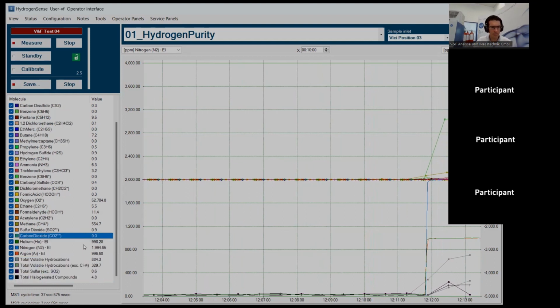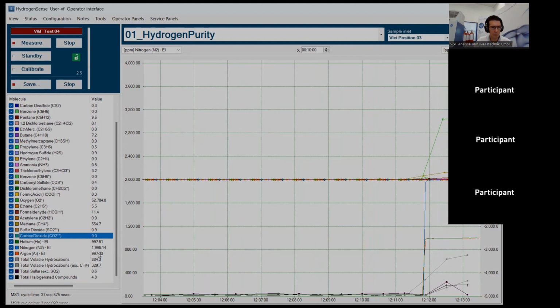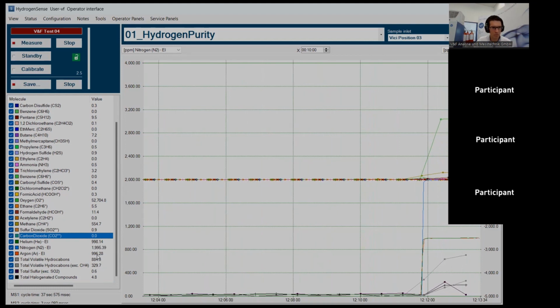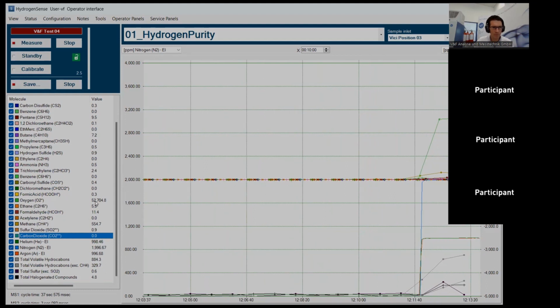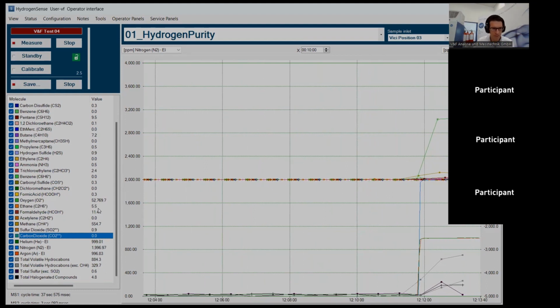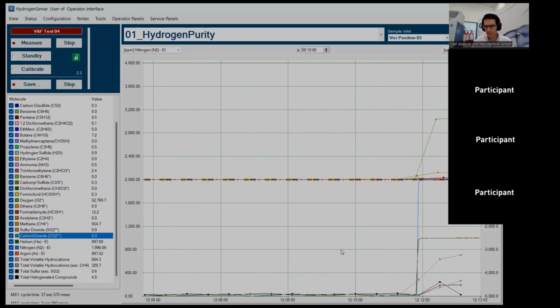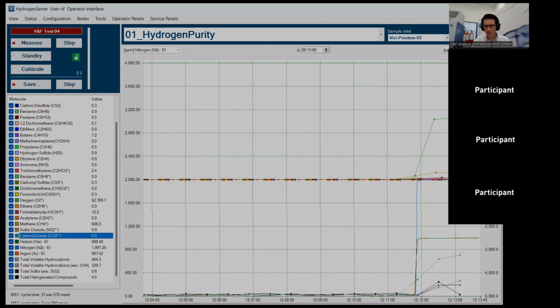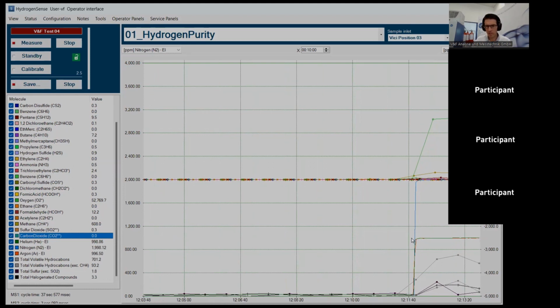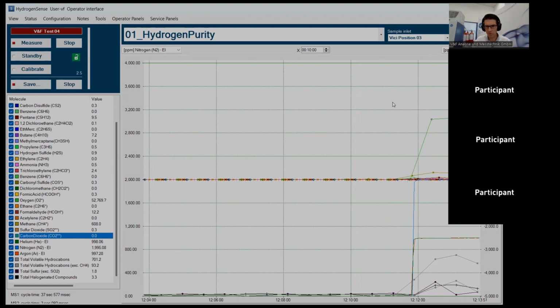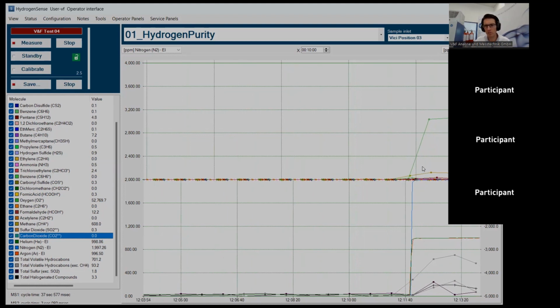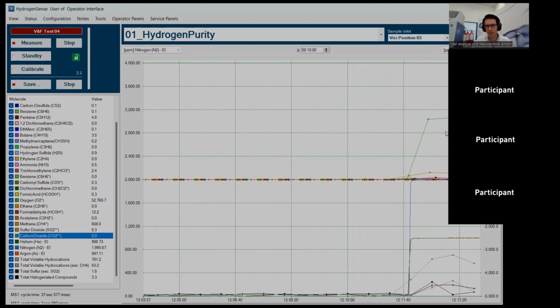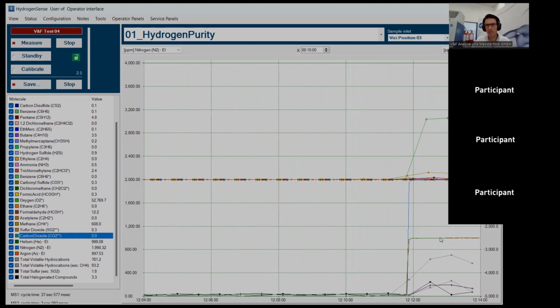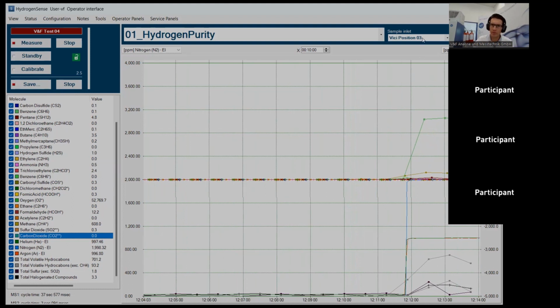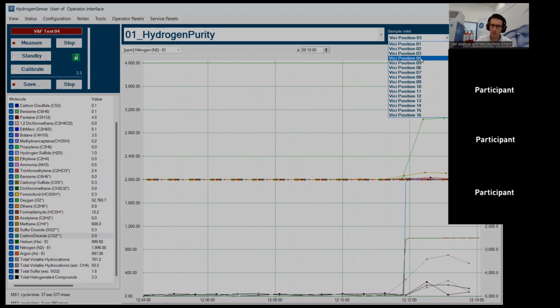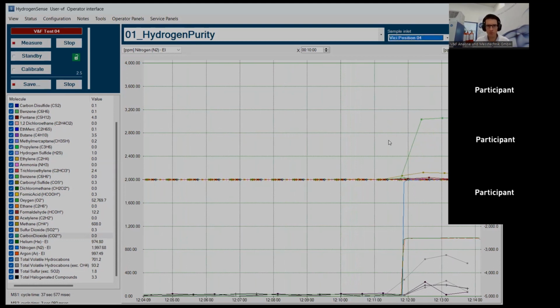And for example, here on this gas, we will see we have 1,000 ppm of helium, 2,000 of nitrogen, and 1,000 of argon. And we have roughly 50,000 ppb of oxygen in this bottle. And you see here the change in signal, so the response time is pretty fast. You pretty much switch over the position, you apply the new gas to the spectrometer, and then the instrument will show the values in this gas. We can maybe try and switch to another bottle, which is connected to position 4.